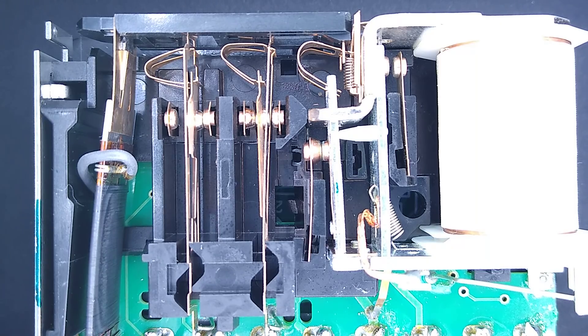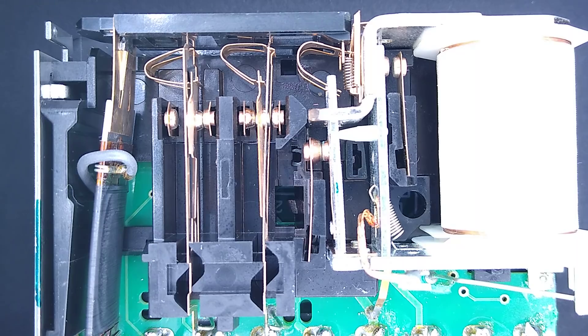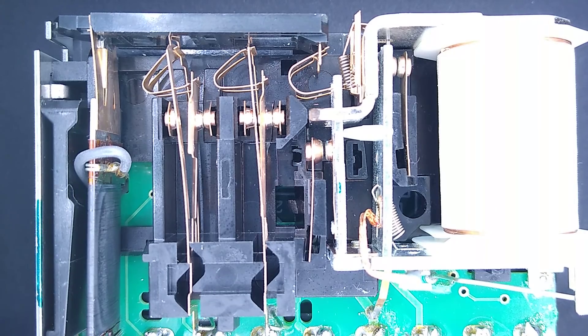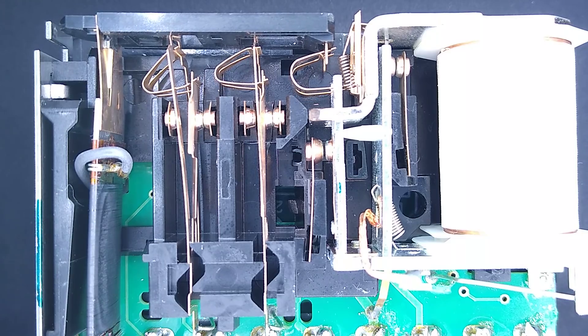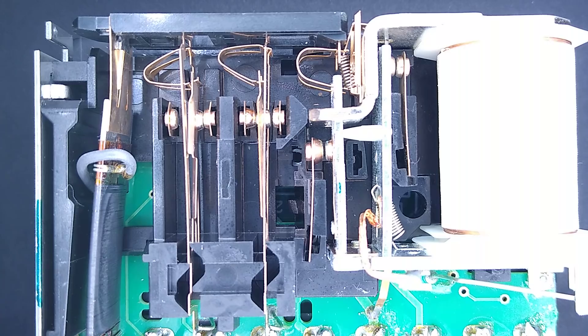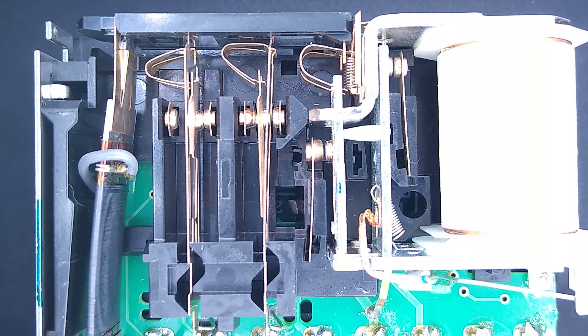Okay, let's take a look at a different scenario. Scenario two: the flame detector is faulty and is continually detecting a flame. The cycle starts as normal, but the coil is trying its best to actually go across. Now the magnetic remnant stops the oil valve closing its relay, and although that can click over, it still can't go over all the way. It remains powered.